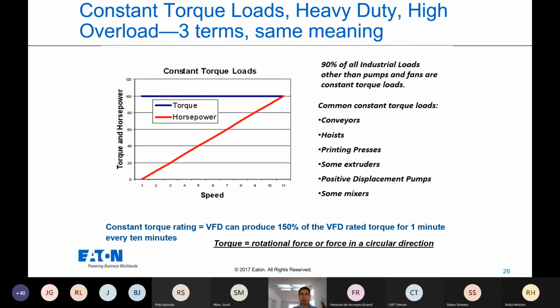So here is an example. We are going to discuss constant torque loads and variable torque loads. So what does constant torque mean? If you've worked with positive displacement pumps, this is a very common application. You have constant torque with changing speed. So what you do here is 150% of your torque rating can be achieved for 1 minute every 10 minutes.